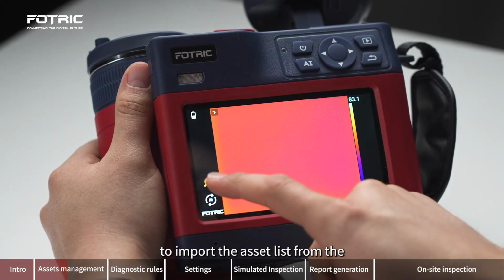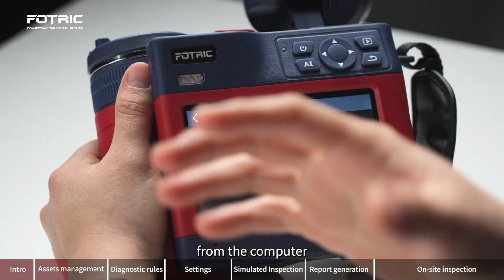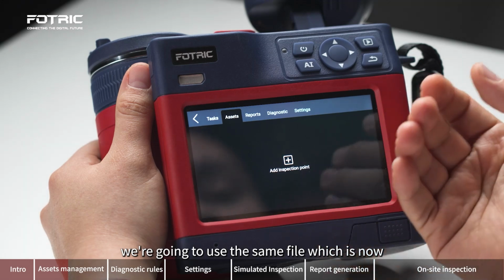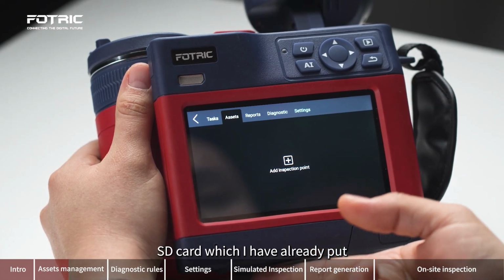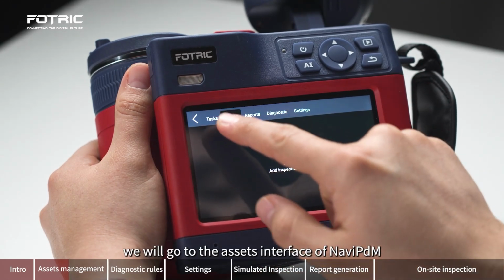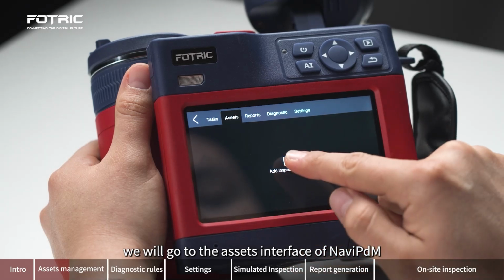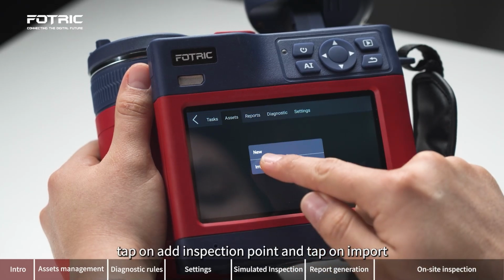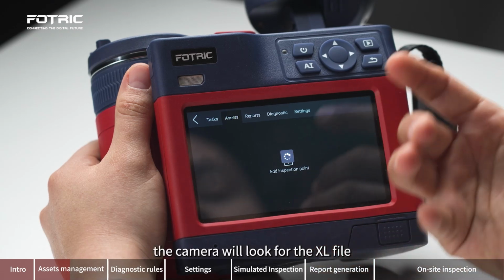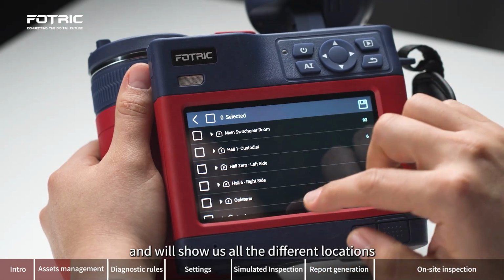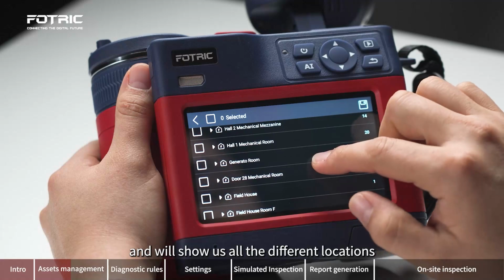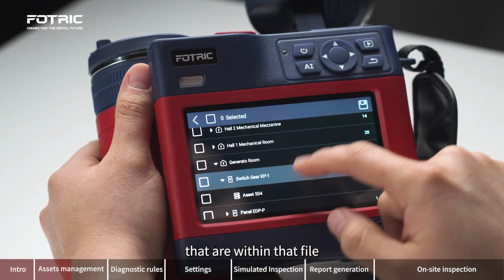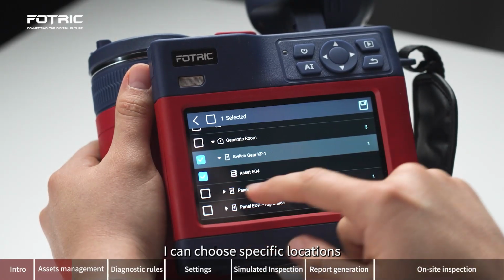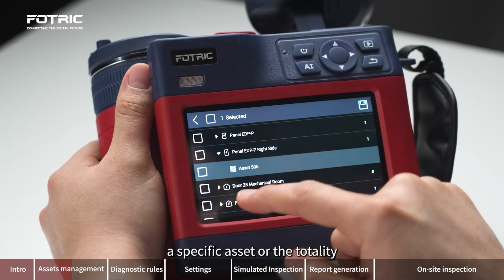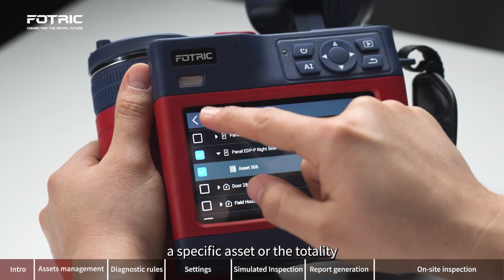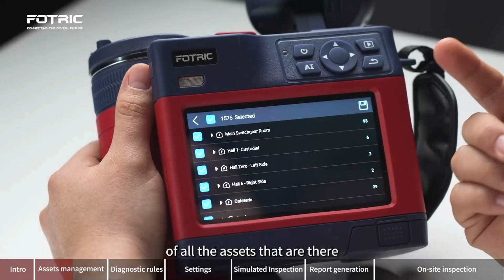To import the asset list from the Excel file or spreadsheet from the camera, we're going to use the same file which is now stored in the SD card, which I have already put back into the camera. We will go to the Assets interface of NaviPdM, tap on Add Inspection Point, and tap on Import. The camera will look for the Excel file and will show us all the different locations that are within that file. I can choose specific locations, specific assets, or the totality of all the assets that are there.